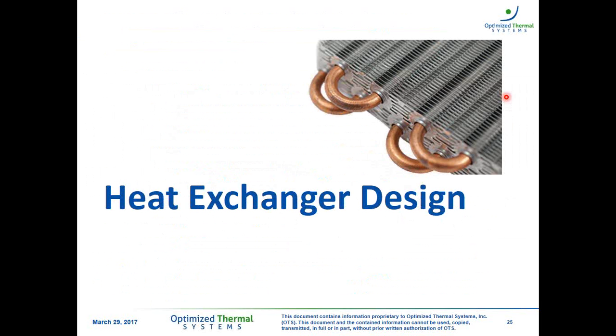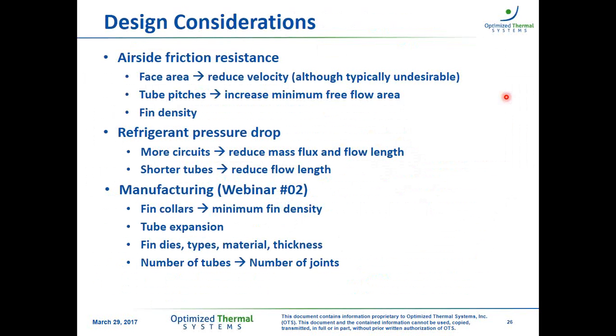Now, how do these things translate into a heat exchanger design and some of the considerations that we need to have? Let's go back to the friction resistance that we mentioned before, and for the air side, how can we approach it in order to reduce the pressure drop? One way to do so is by enlarging the face area to reduce velocity. Although this is typically undesirable because in terms of space occupation, the face area may be more important than other geometrical aspects of the heat exchanger. But if that is a degree of freedom, this is one way to reduce the actual pressure drop by reducing the velocity and still get high heat transfer coefficients.